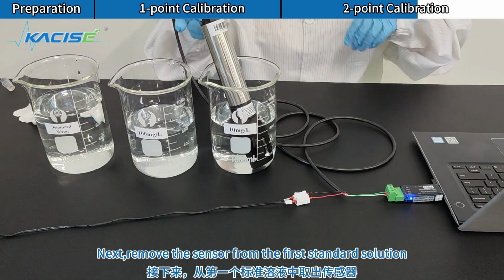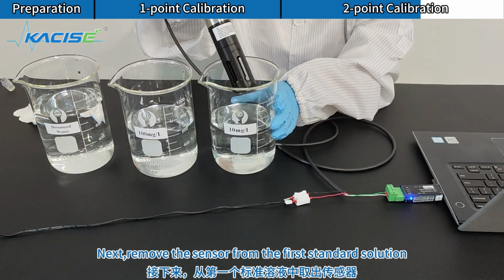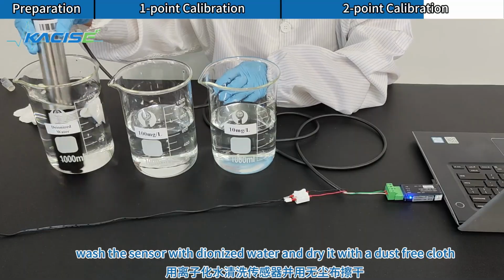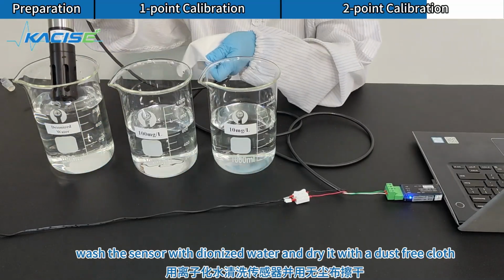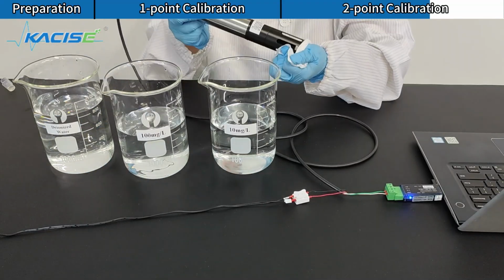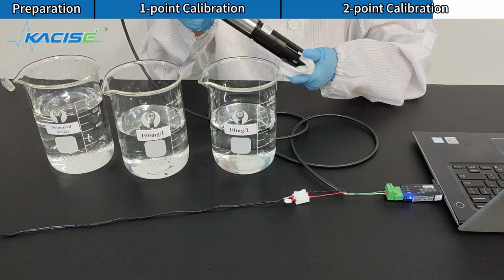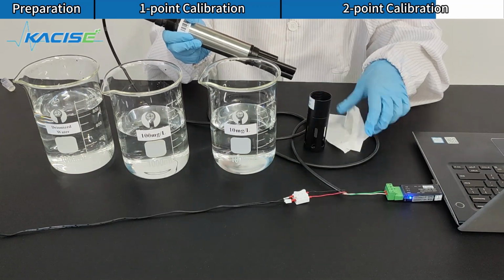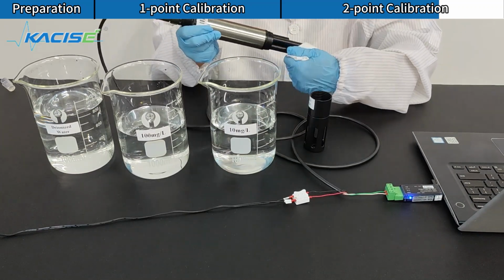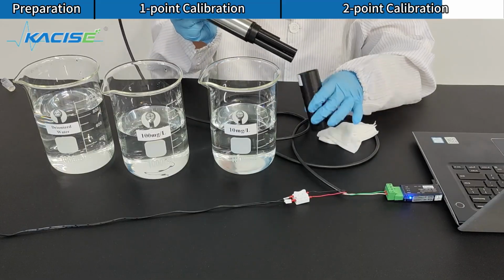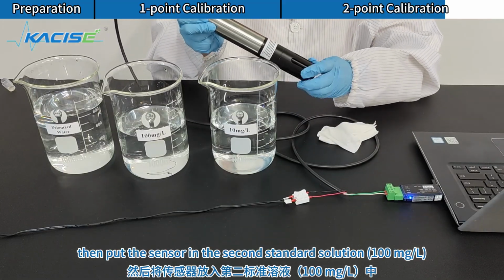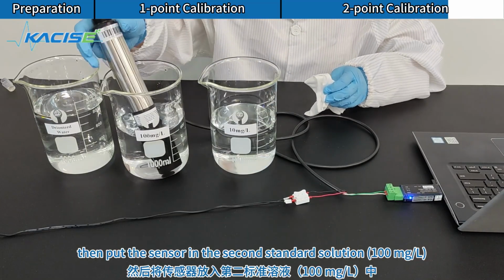Next, remove the sensor from the first standard solution. Wash the sensor with deionized water and dry it with a dust-free cloth. Then put the sensor in the second standard solution, 100 mg/L.